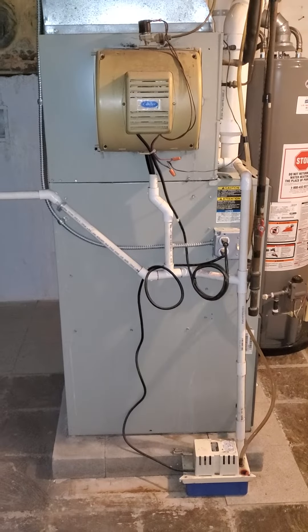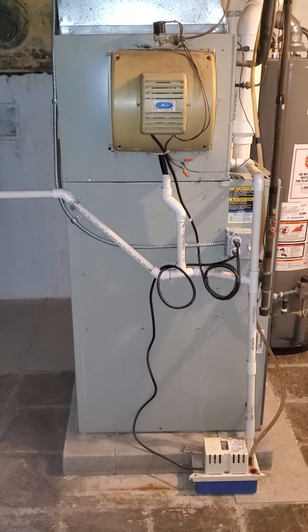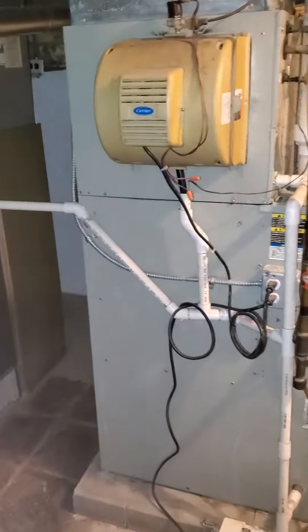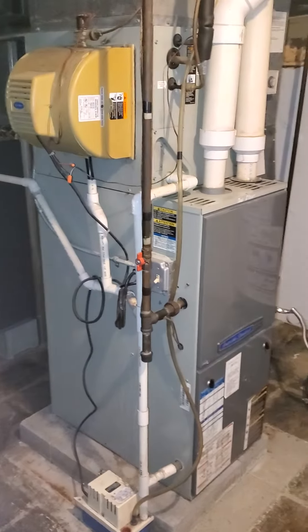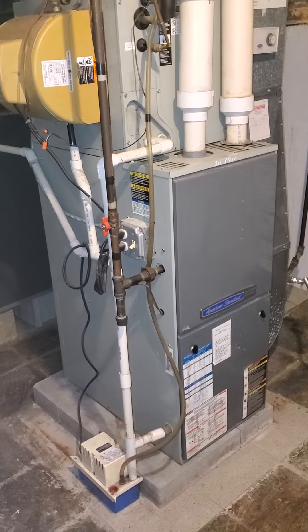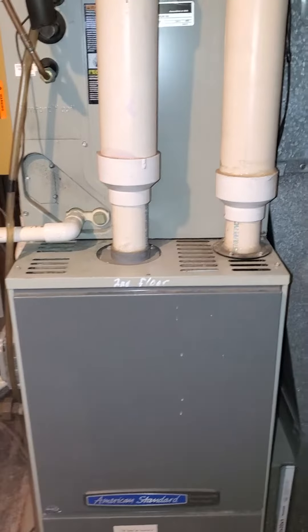Cesar Sanchez, Consultant 898 in Chicago, looking at a 90% efficiency furnace located in the basement of the property. This is an 80,000 BTU unit — 40 inches height, 17 wide, and 28 depth. PVC is 2.5 inches on the lower and 3 inches on the top.